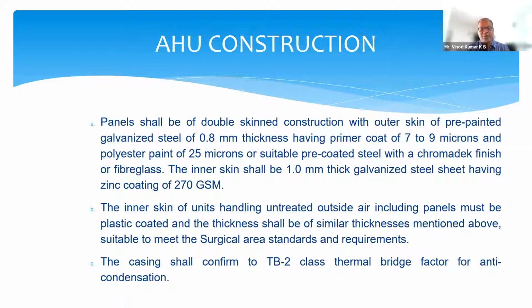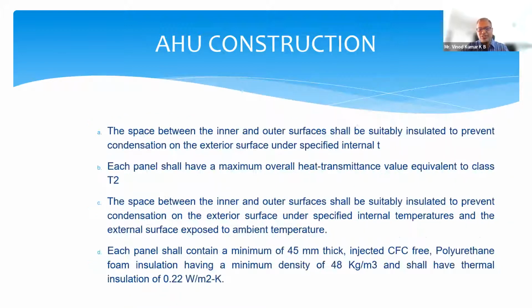This thermal bridging factor is basically to confirm that there is no condensation. When do things condense? Because there is something cold on one side and something hot on the other side, and then you have a metallic surface where condensation happens because of the temperature difference, and when dissimilar metals are touching each other. So you have to have a classification of this casing, which we call TB2. That TB2 actually makes it a thermal bridge, which avoids this connection between the cold and the hot, or the low humidity and the high humid air, high temperature and low temperature air. Thereby, anti-condensation really happens. So TB2 is an important factor in your selections.